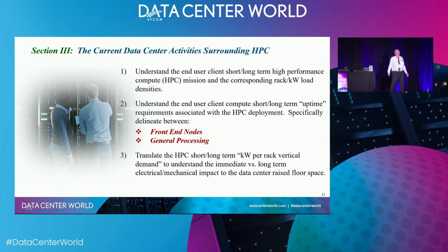A classic example, we just got done discussing with a utility company and said, hey, we need 2 megawatts right now for an initial high-performance compute installation pod, but we reserved 10 megawatts. So we have a 13-2 line that can actually drive 10 megawatts, actually 2 of them. We're cutting down to 2 megawatts now because we know in the future it's going to be unbelievable. But just having some forethought with that, they can bring in the lines, size the capacity, then work with their substations about how to go and deliver that.